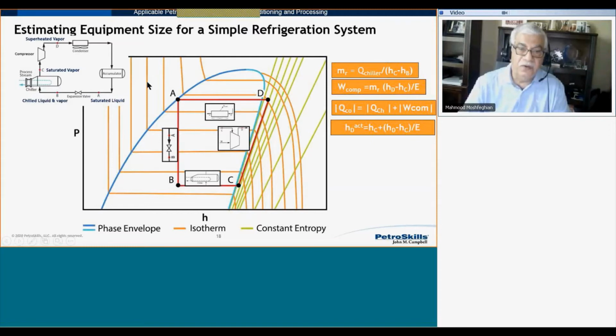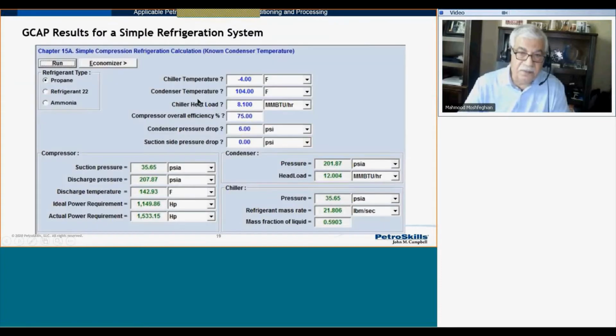The orange color are isotherms, and during the phase change, the temperature remains the same, and we see constant temperature extending all the way down to the gas phase. These are higher temperature compared to the lower temperature here. And in addition, we have the greenish color is a constant entropy line, or isentropic path, we call it. So let's see how we can use pH diagram to size our equipment. When we enter the expansion valve, we have saturated liquid with known temperature. So if I know temperature, I draw a horizontal line, identifying my known temperature.